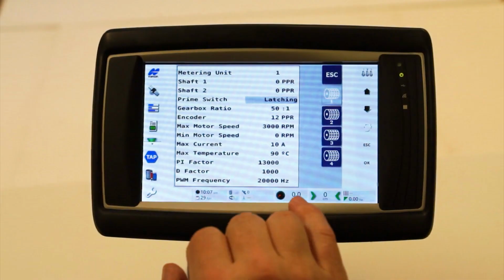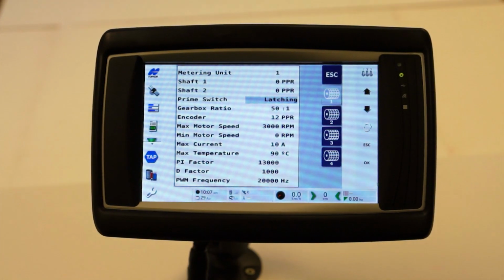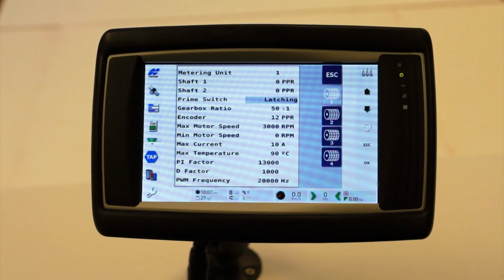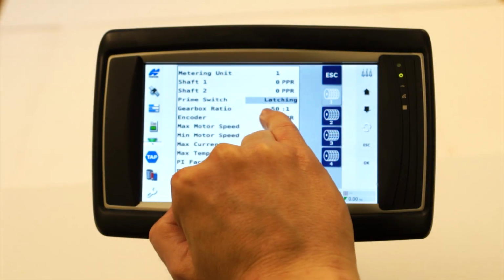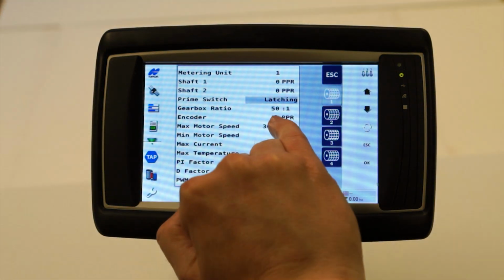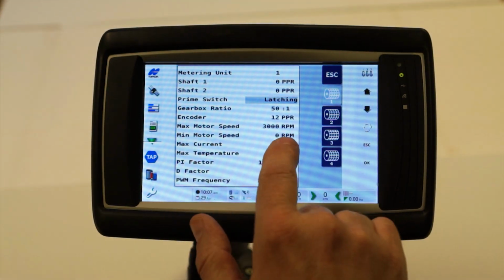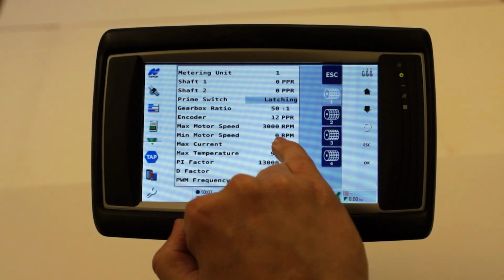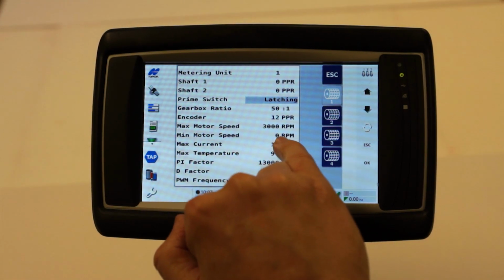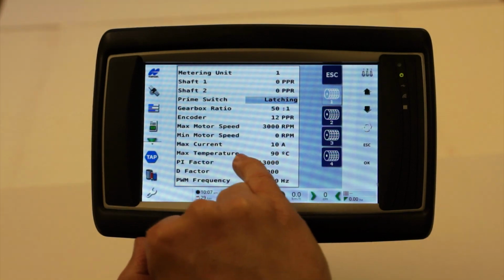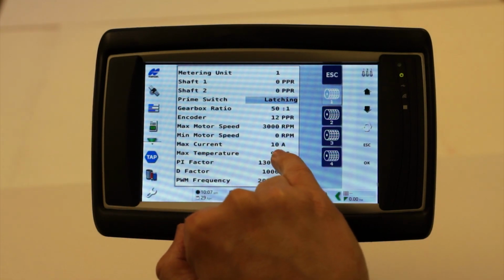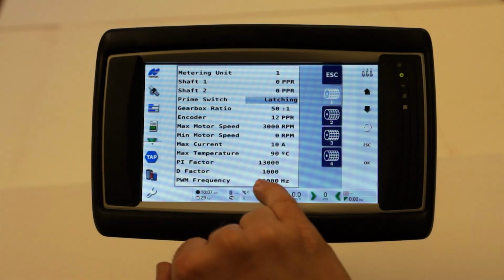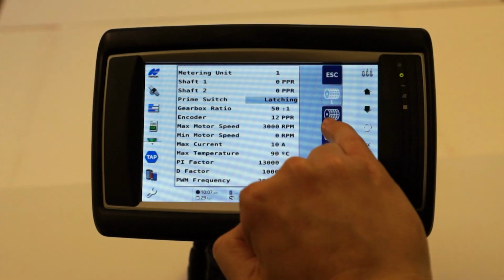And then in the metering setup, this is where you have to follow the instructions very clearly to get these ratios correct, otherwise the machine will not work properly. So you check that shaft 1 and shaft 2 are set to 0 pulses per revolution, prime switch to latching, gearbox ratio important 50:1, the encoder is 12 pulses a revolution, and then you have the maximum motor speed of 3000, minimum motor speed to 0. Change the max current for the motor to 10 amps, and then these underneath don't need changing, and this is all dependent on what channel we're working on. So on this machine we're on channel 1.